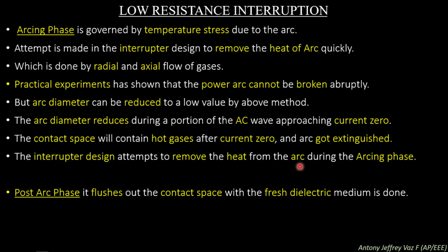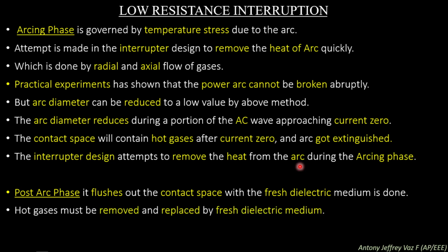In the post-arc phase, the contact space is flushed out with fresh dielectric medium. In the post-arc phase, we are removing this hot gas by flushing a new gas or new dielectric medium into the space where the arc is ionized. These hot gases must be removed and replaced by fresh dielectric medium to stop the arc when the rising current wave occurs.